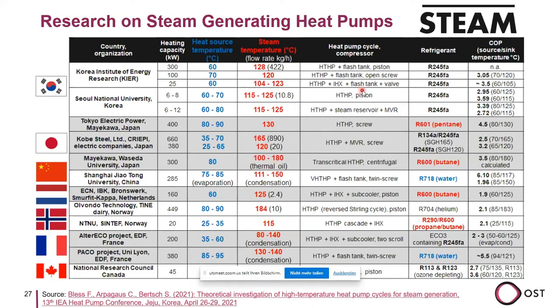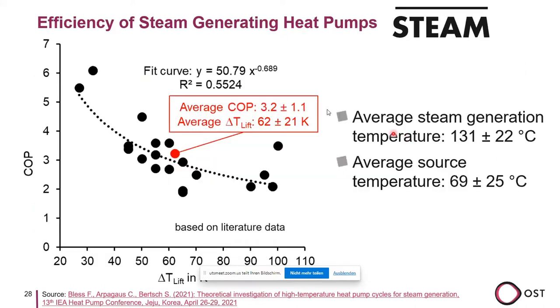And the cycles are shown here, and the compressor types and the refrigerants which are used, and some data of COP. I don't want to go into more detail. I just put the COP data in another graph, as a function of the temperature lift, and we can also recognize this trend for the COP. An average COP is around 3.2 at 62 Kelvin lift.